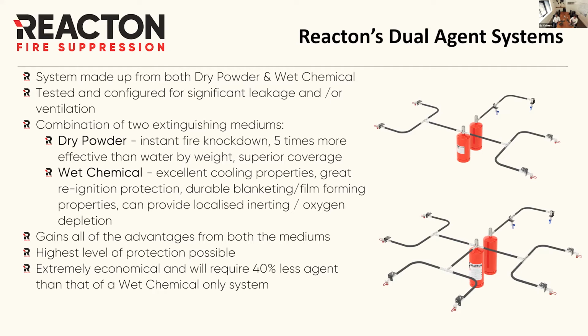It's made up from a dry powder or dry chemical system along with a wet chemical. They're tested, configured for significant leakage and ventilation. And actually from our testing, you could have essentially an engine in the middle of a field and still protect it, even with high airflow. And that's something that we evaluate when we go through our design criteria and risk assessments.